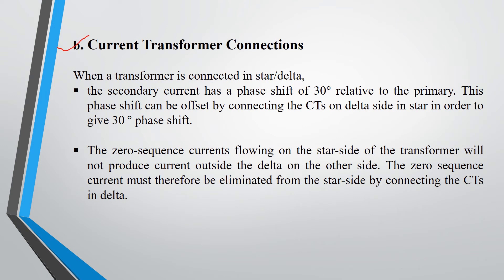The second consideration is current transformer connections. Taking transformer connections in star-delta — that is, the primary winding connected in star and secondary winding connected in delta — the secondary current will have a phase shift of 30 degrees relative to the primary current, and this phase shift needs to be taken care of. Otherwise, the CTs connected on both sides of the transformer will respond in a different manner. Thus, the CTs on the delta side are connected in star to compensate for that 30-degree phase shift.